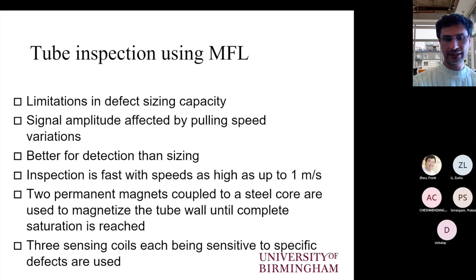So typically, it has to be transverse, the orientation of the crack with respect to the flux lines, because if it's running longitudinal, then the flux leaking will be too low and will probably go undetected. So two cracks of the same size, depending on their orientation, can be the difference in detecting them or not detecting them.